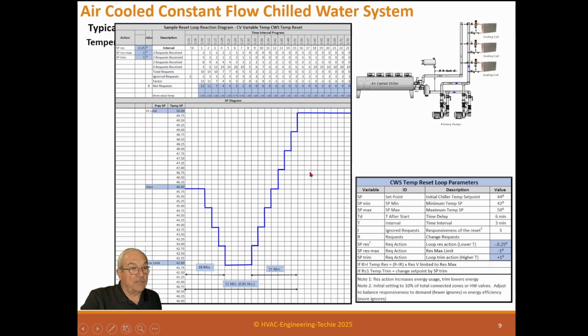Now you may have set this at 48, so maybe 48, but the times are small. So this is 21 minutes, and 21 minutes is doable. Really, for the reactions from tenants and everything, a half hour is reasonable. If temperature goes out of range a little bit and in 15 minutes it comes down, you're not going to have any big complaints about that.